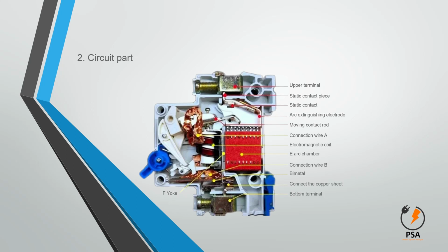Here you can see the circuit part of an MCB. When the contact is closed, the rated current flows in the circuit. When the contacts are separated, an arc current is generated between the contacts. The current path initially runs through the arc path. After the arc is introduced into the arc extinguishing chamber E due to magnetism, heat, etc., the current path is E and F. The arc is divided into 10 segments in the arc extinguishing chamber, which are quickly cooled and extinguished. After the arc is extinguished, the current is completely interrupted.